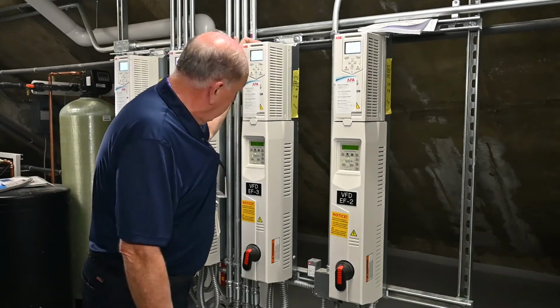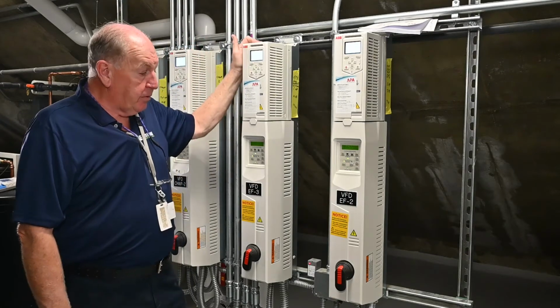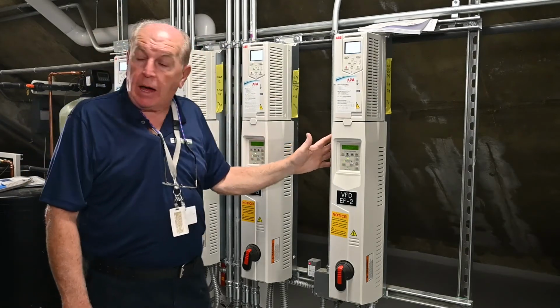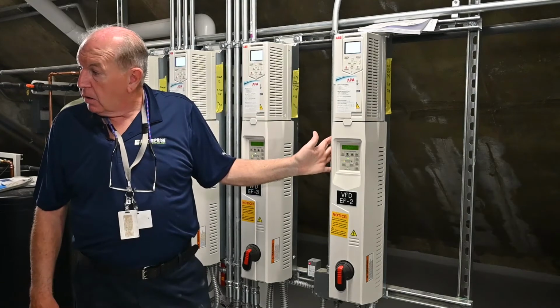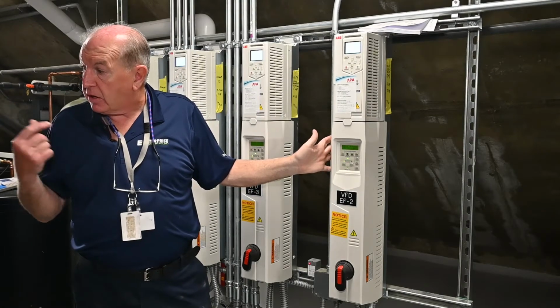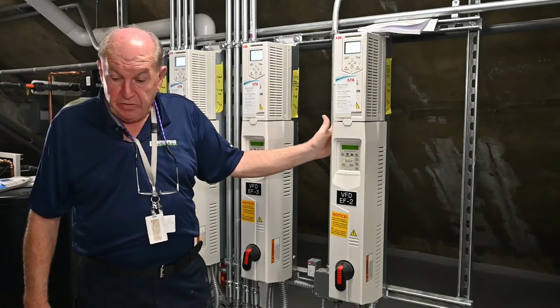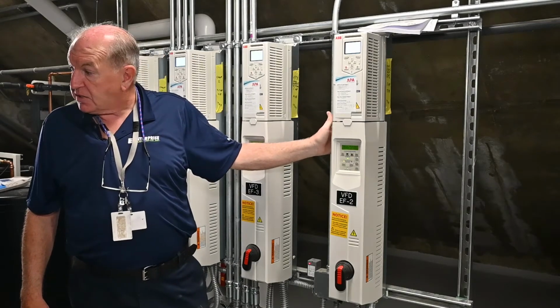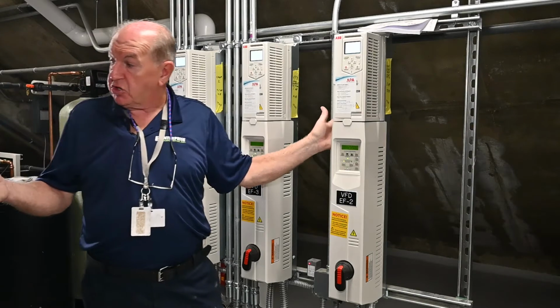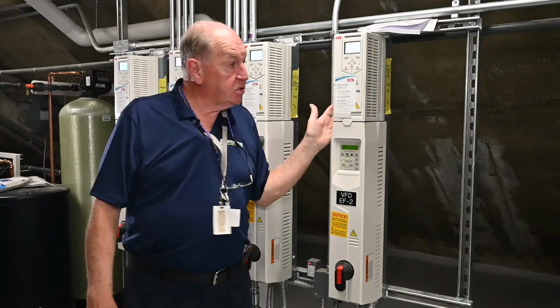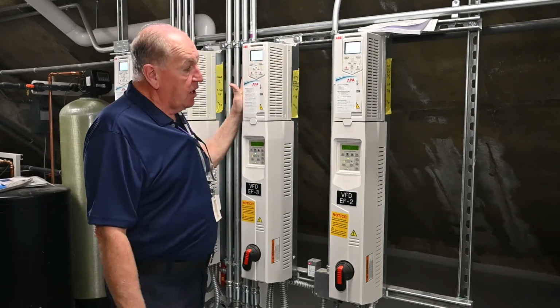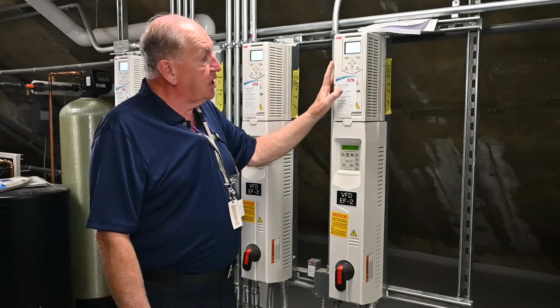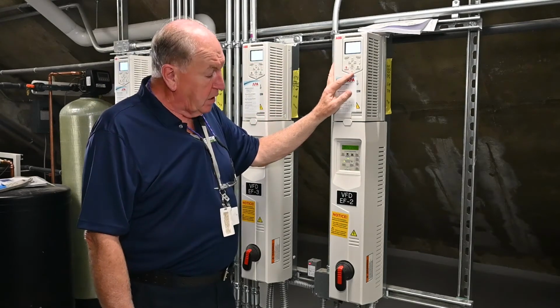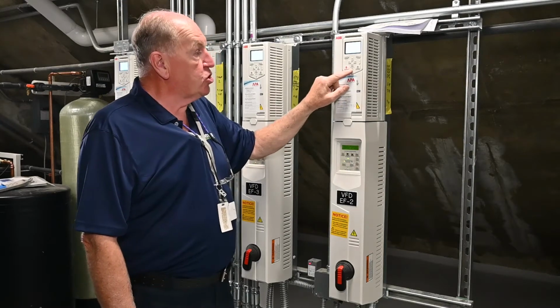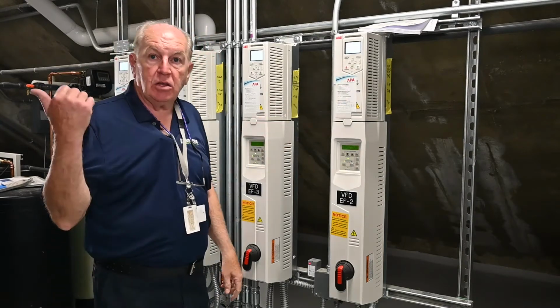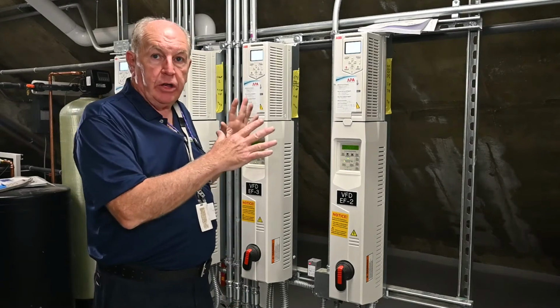That's EF3. And we'll also be looking at EF2, which is the dump fan on the return air. If we have too much return air, we have to exhaust some of it. So EF2 is a 5-horse exhaust fan up on the roof, teed into the return air ductwork. So it's the same drive. It's an ABB drive, so same thing, same reset, same everything you're looking at should be an automatic, and then the building management system will control it.